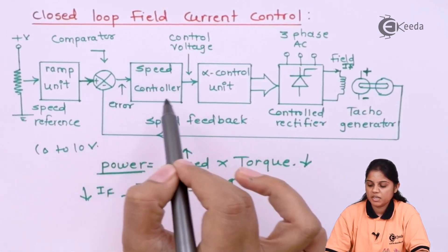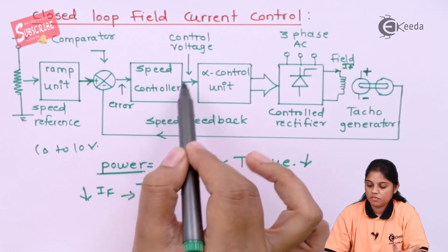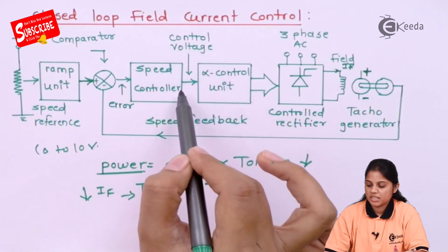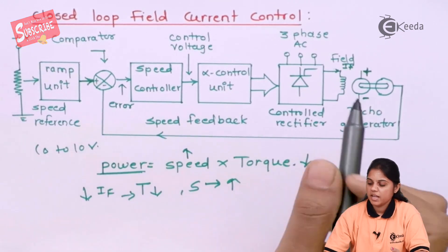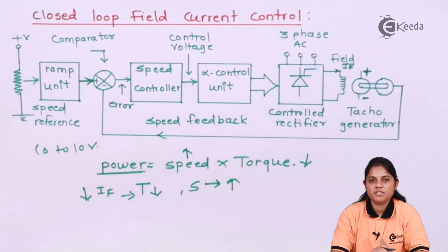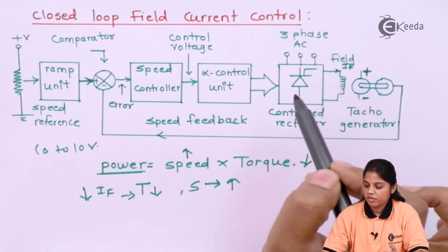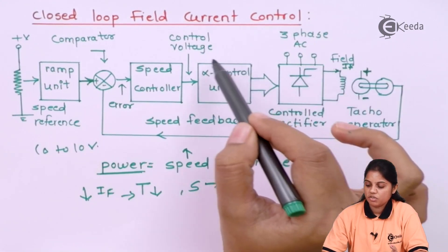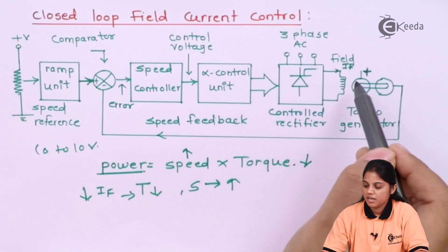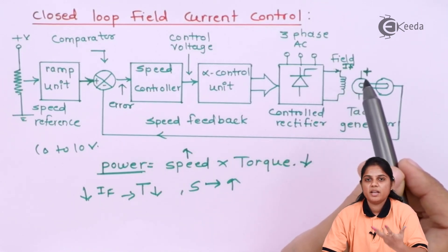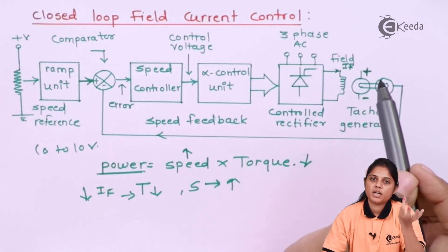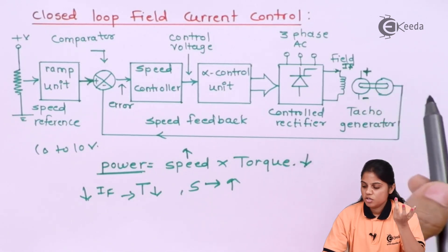That error is given to the speed controller. Then the speed controller will produce a control voltage that is given to the alpha control unit. That will change the firing angle of the thyristor and then thyristor operation will change to vary the current. If thyristor operation changes with the help of change in firing angle, the current will also either increase or decrease. And depending on that, if current increases your speed will decrease, but if your current decreases your speed will increase.